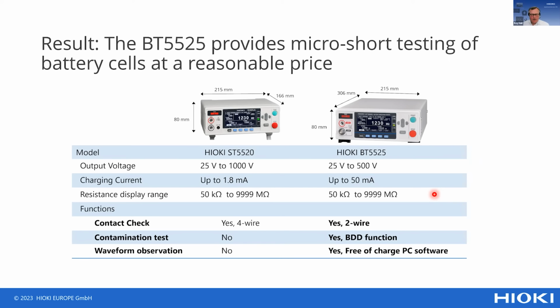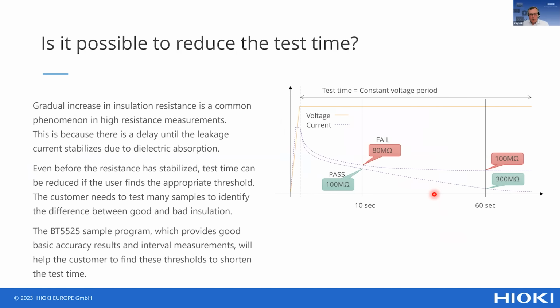And then another question. You showed measurement times of 10 to 60 seconds. Is this the recommended duration for each measurement, or can it be reduced once parameters are set? Basically, this is more of an indication of what we also see in the market, that the test voltage is being applied for around 60 seconds. And this is when typically the test is being finished. And based on the statistical data the device is collecting, you have the capability to already say or assume that after 10 seconds, we see this resistance value, and we assume that after 60 seconds, it would lead to this.